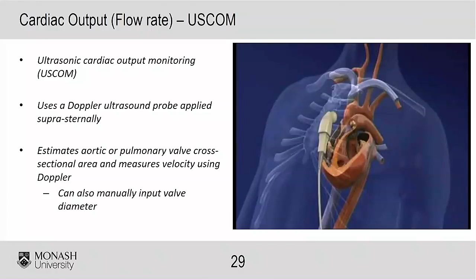So the way it essentially works is it sends ultrasonic pulses by the transducer. Stationary particles will always send back the same signal, so it has some software filtering that basically filters stationary things out, whereas moving particles send back different signals. Now, interestingly, here you can see how it calculates the velocity of the blood. It's going to have some Doppler things there. It's going to need to know the speed of sound in the tissue. But we've also got the angle of incidence between the ultrasound beam and the direction of flow.